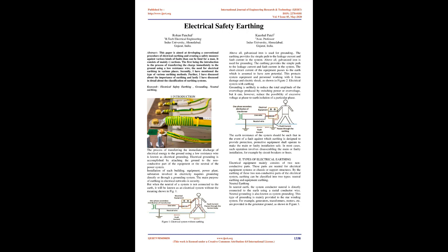In neutral earthing, the system conductor neutral is directly connected to the earth using a metal conductor wire. Neutral grounding is also known as system grounding. This type of grounding is mainly provided to the star winding system, for example generators, transformers, motors, etc. It is provided in the generator ground, as shown in Figure 3. Figure 3, Neutral and Equipment Earthing.